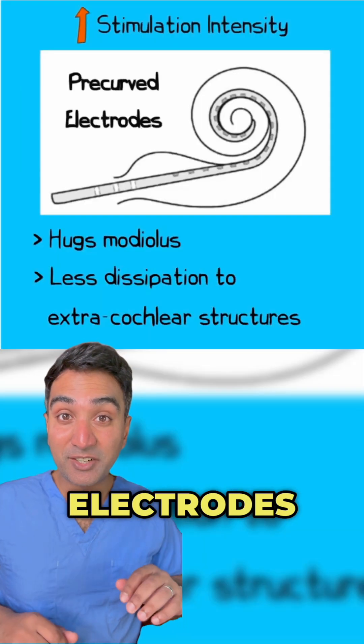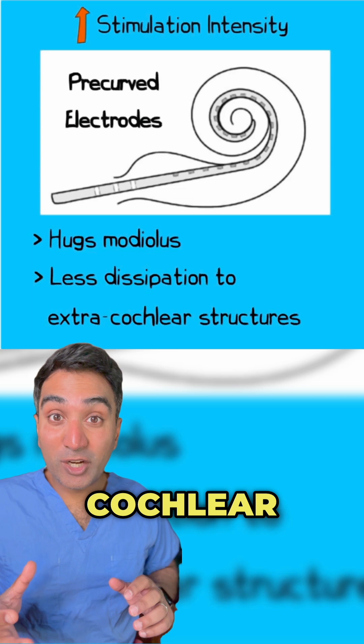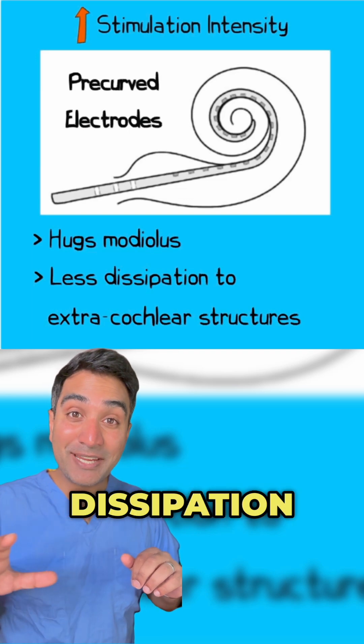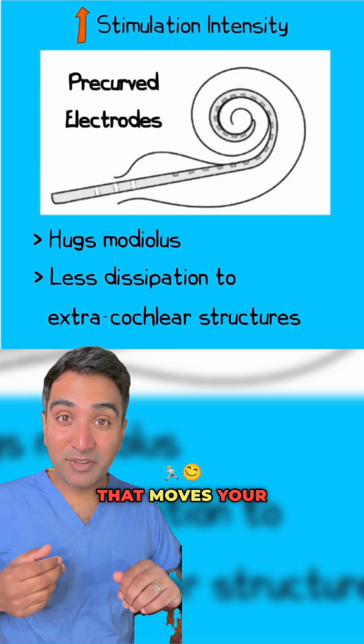Pre-curved electrodes are designed to hug the modiolus of the cochlea, the bit where all the cochlear nerve endings are located. This enables greater stimulation of the nerve at a given energy level, and also less energy dissipation to structures outside of the cochlea, such as the nerve that moves your face.